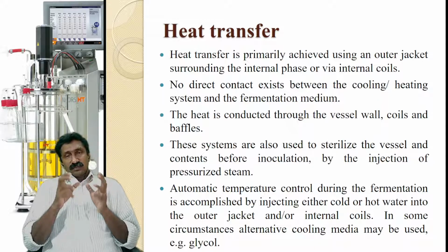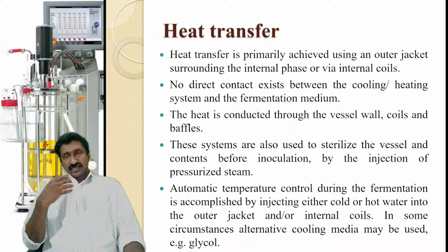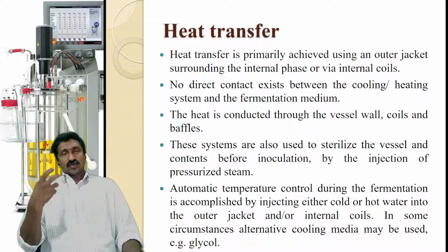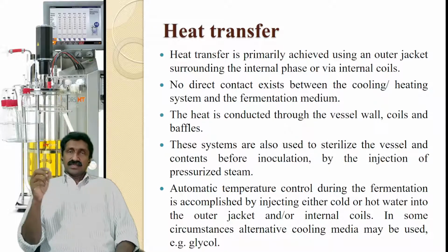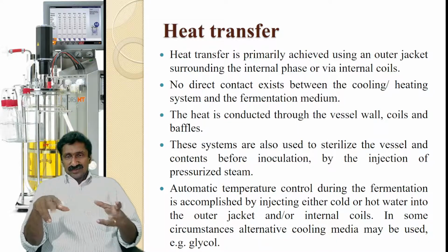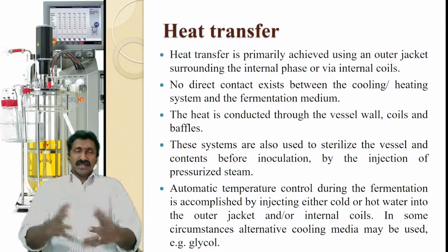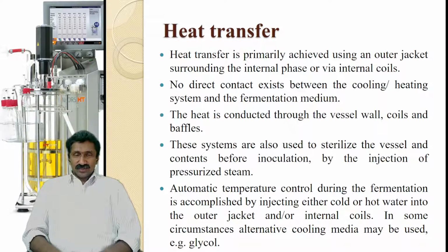Now, temperature control during the fermentation is accomplished by injecting either cold or hot water into the outer jacket or the internal coils. So actually, you cannot inject hot water directly into the medium, because it will get diluted and destroy the medium.